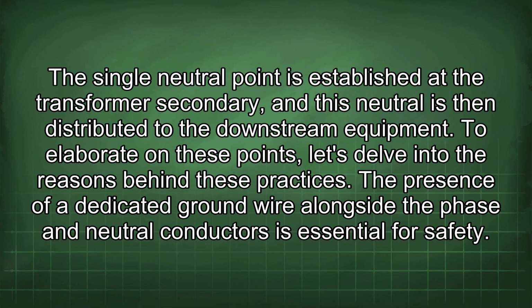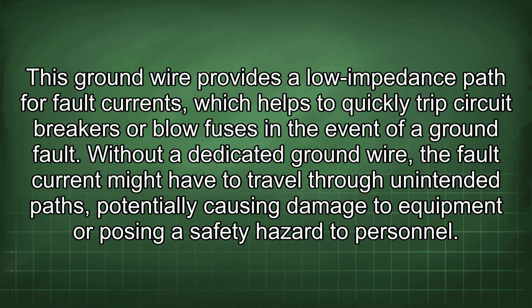The presence of a dedicated ground wire alongside the phase and neutral conductors is essential for safety. This ground wire provides a low impedance path for fault currents, which helps to quickly trip circuit breakers or blow fuses in the event of a ground fault. Without a dedicated ground wire, the fault current might have to travel through unintended paths, potentially causing damage to equipment or posing a safety hazard to personnel.